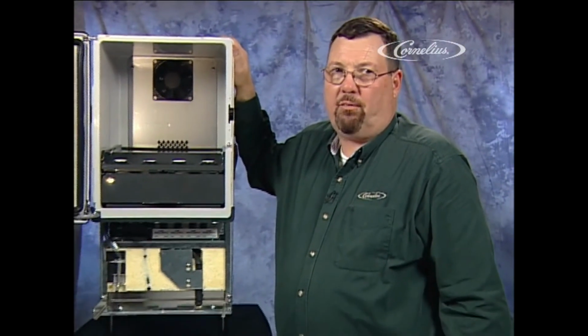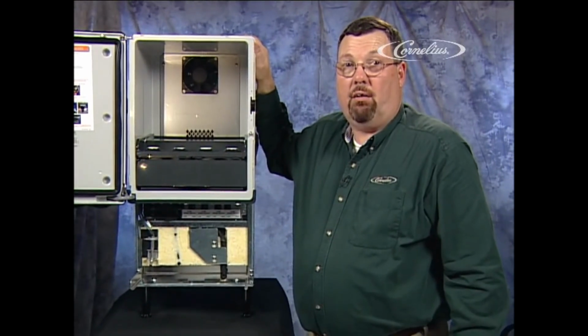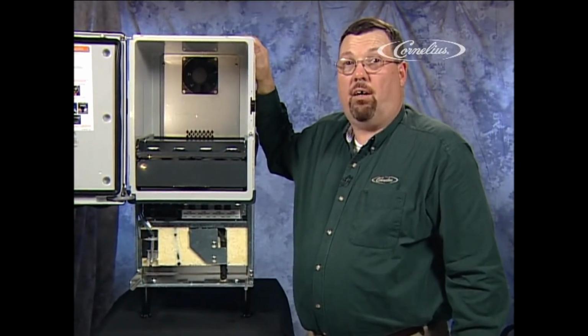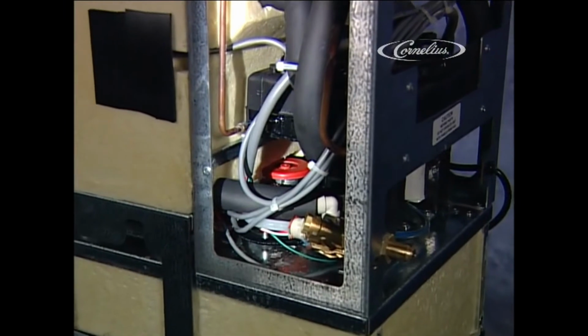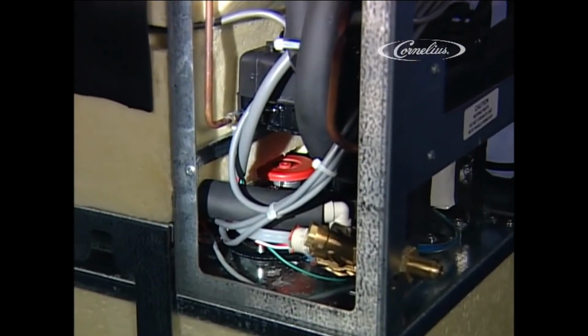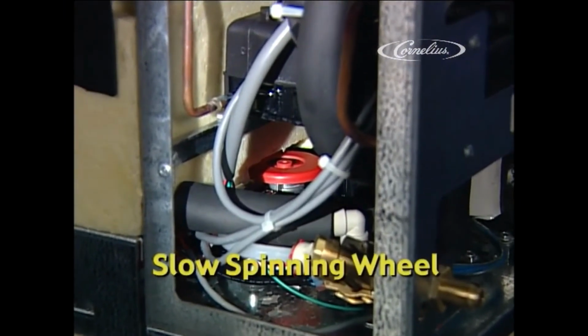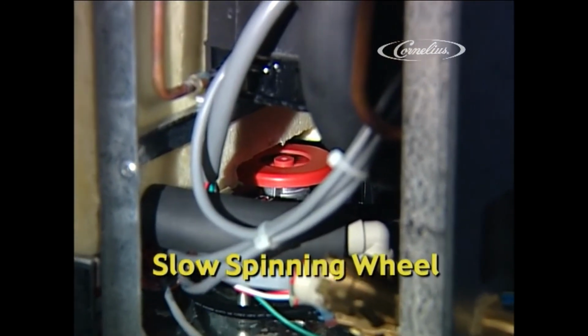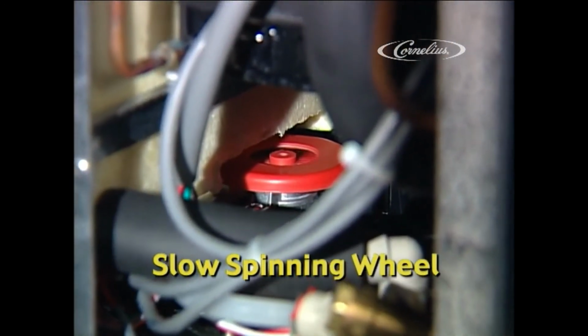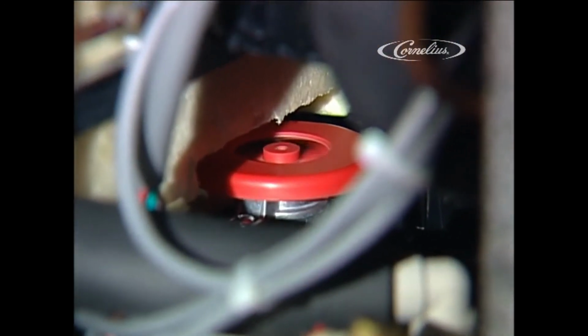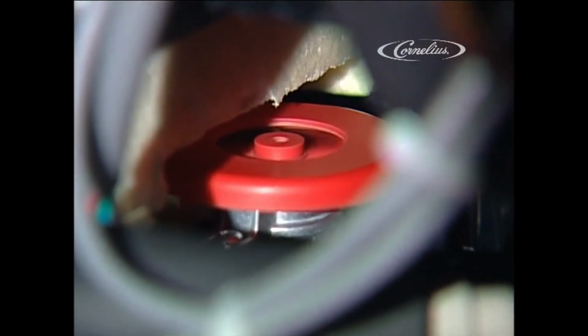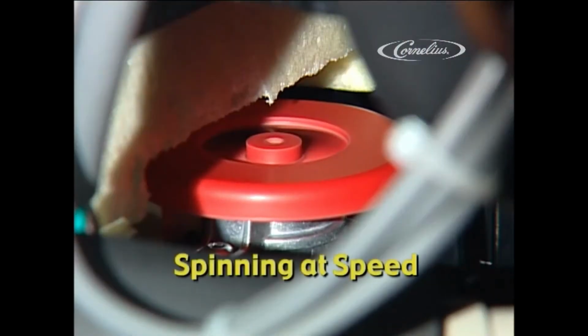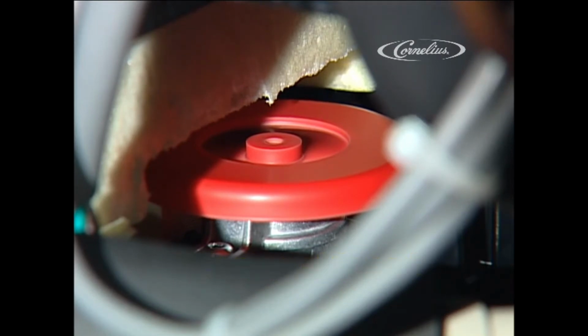If you experience a warm cabinet and the water from the valve is at least 40 degrees or below, then the agitator motor is at fault. First, you check to see if the red wheel mounted to the motor is spinning slowly or not at all. If it's spinning slowly, you are not sending the cold water into the heat exchanger, therefore no cooling is taking place. This and the cabinet fan both run when the unit is plugged in. There is no on-off on this system. Refer to the training manual for removal and replacement of this motor.